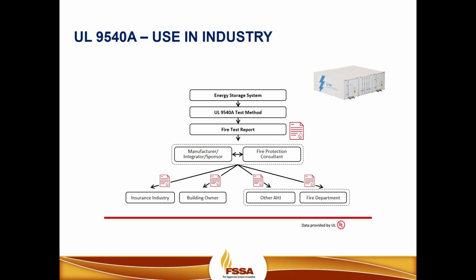So if you were to have an energy storage project in your particular jurisdiction, and let's say hypothetically you were using or looking to use, say, Samsung type batteries or maybe LG Chem type batteries, you can reach out and contact UL as an AHJ or a fire consultant and request these reports that were conducted. These are critical parts of the risk assessment, and they'll even document if and how an off-gas monitor was used or present and what type of results were seen.